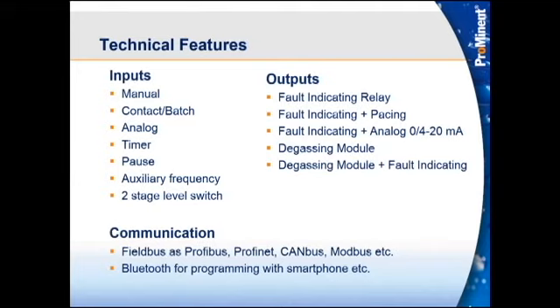You now have the ability to change it from being normally open or normally closed. Okay. So in the past, that brown and black wire had to be together or the pump would be in pause. Now I can change it so that brown and black wire can be open and the pump will be out of pause. Okay. Just more flexibility for SCADA operators, some of our guys that are doing the programming. That auxiliary frequency, if you ever use that, we were only able to adjust the frequency with that. We can now have it adjust the frequency and the stroke length. So I can make that go to a true 100%.